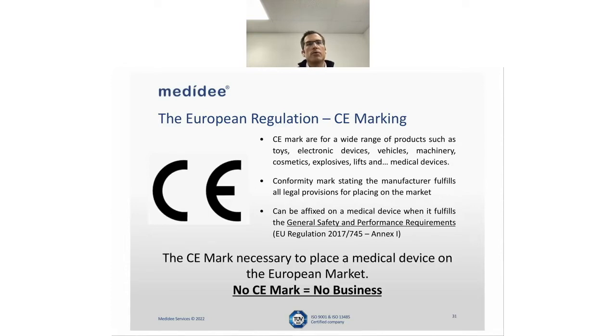One thing which is really important to keep in mind: the CE mark is not a marketing tool. It's not a nice to have, or something we get for the investor. It's mandatory to have on your device. So you need to go through this process, the conformity evaluation process, to be able to place the CE mark on your device. If you don't have the CE mark, it means you have no business, so you're not able to sell your device. You also have to keep in mind that once you get the CE mark, it's not forever, so you have to maintain it. As we'll see a little later with the interaction with the notified body, you need to perform some actions on a continuous basis in order to keep your CE mark. If you lose your CE mark, your device can no longer be placed on the market.